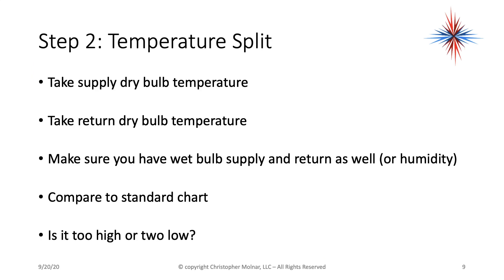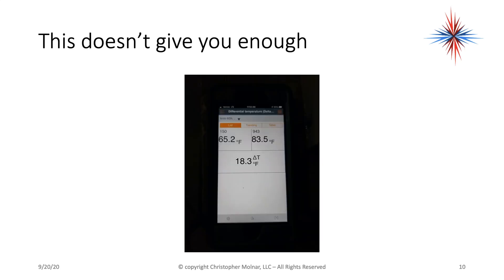Then we go inside and take a look at the temperature splits. We take our supply dry bulb temperature and our return dry bulb temperature. We make sure we have a wet bulb of each as well, or the humidity. We compare it to a standard chart. Is it too high or too low? Just standard dry bulb temperatures alone does not give you everything you need.